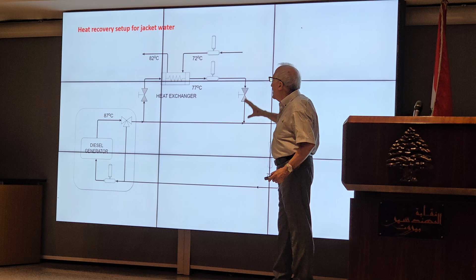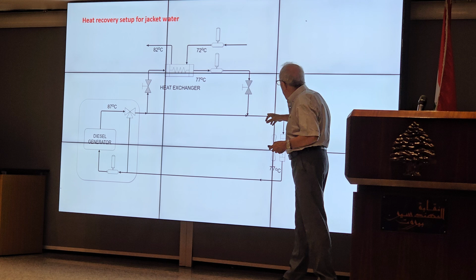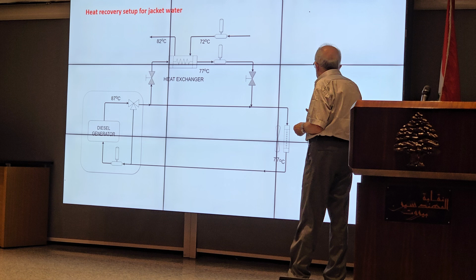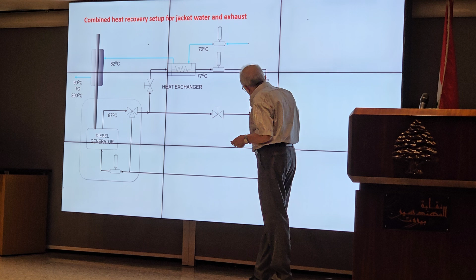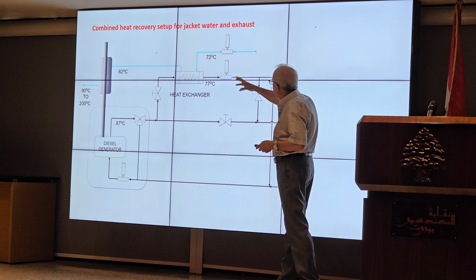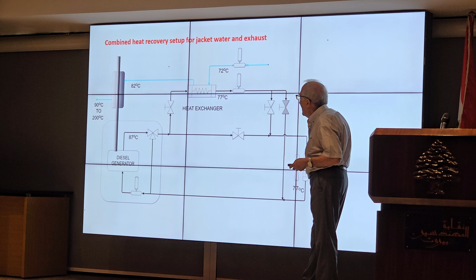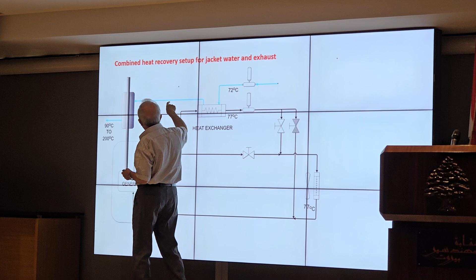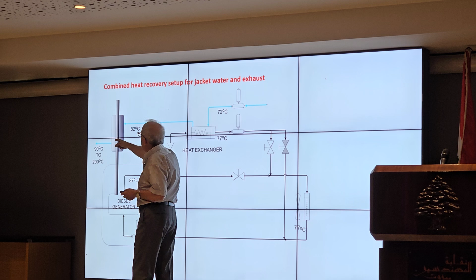The drawback is that with this setup we can have maximum 65% recovery of the heat, because the heat that is coming out here is still hot, and there is a heat rejection to the outside here. Another one, which is a little bit more complicated, is that instead of re-injecting at this stage, when the system is on, we re-inject after the heat. And in this case, we can go up to 85% efficiency in recovering the heat. In this setup we had water at 72, heated to 82, and then with the exhaust to 90 or even more. It is pressurized water, you can go to 200 degrees C.